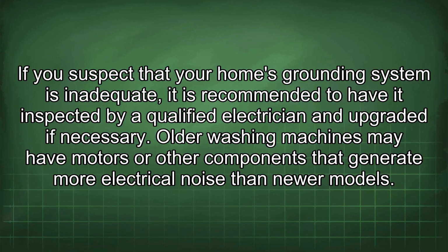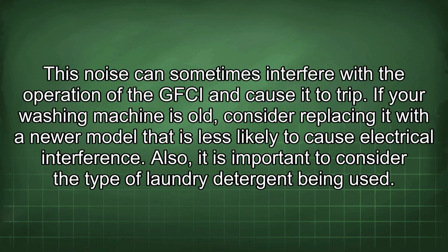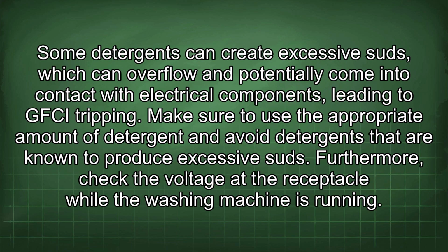Older washing machines may have motors or other components that generate more electrical noise than newer models. This noise can sometimes interfere with the operation of the GFCI and cause it to trip. If your washing machine is old, consider replacing it with a newer model that is less likely to cause electrical interference. Also, it is important to consider the type of laundry detergent being used. Some detergents can create excessive suds, which can overflow and potentially come into contact with electrical components, leading to GFCI tripping. Make sure to use the appropriate amount of detergent and avoid detergents that are known to produce excessive suds.